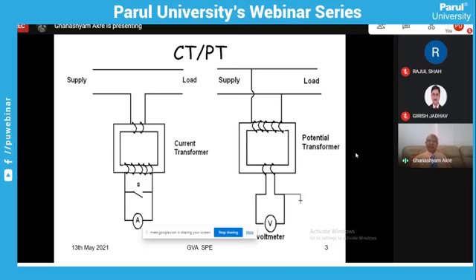At the right side schematic, you can see it is the voltage transformer or the potential transformer. Here the winding of the transformer on the core is completely connected across the power supply. That means if it is 400 kV, all 400 kV will appear across that winding. So unlike the current transformer, where the line comes from high voltage, takes a few turns and then goes back, in the VT the full voltage is applied across the primary winding. And the secondary turns are such that they reduce the voltage to the desired value.